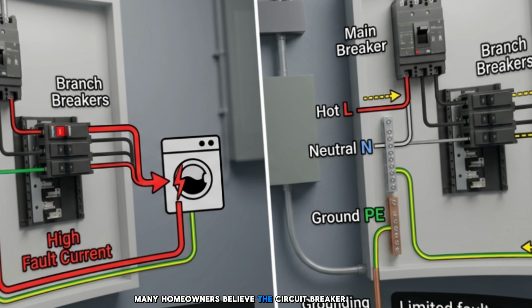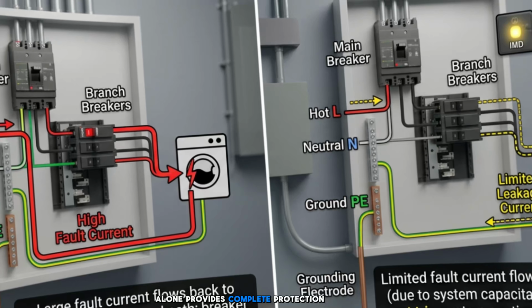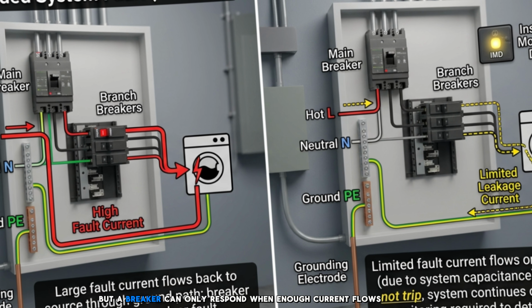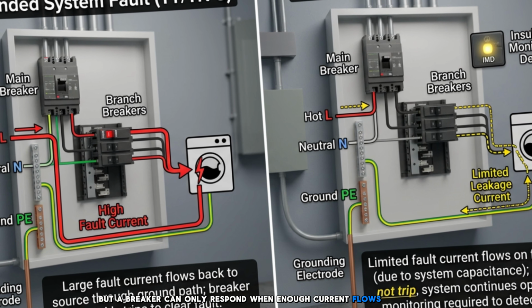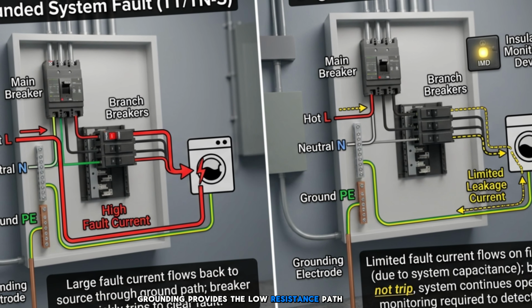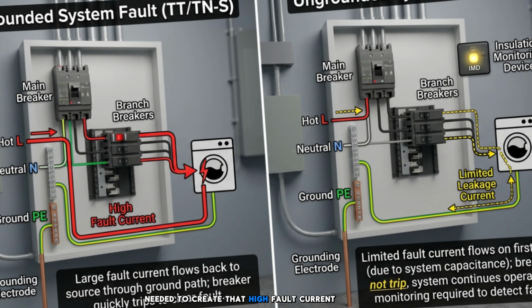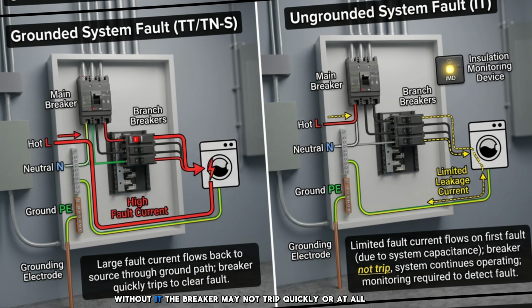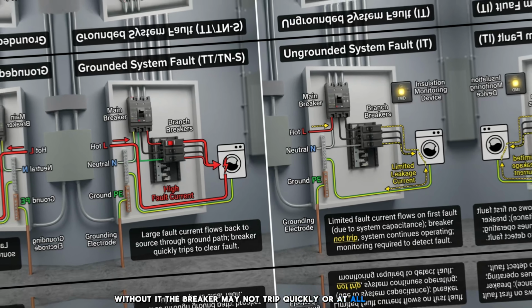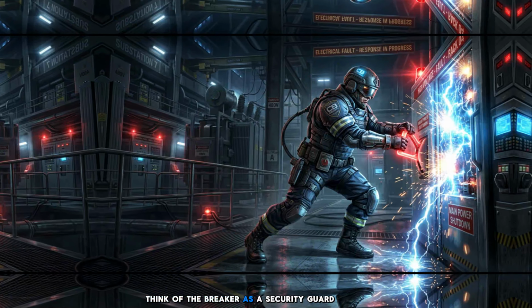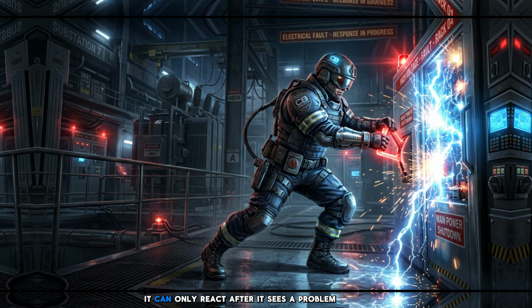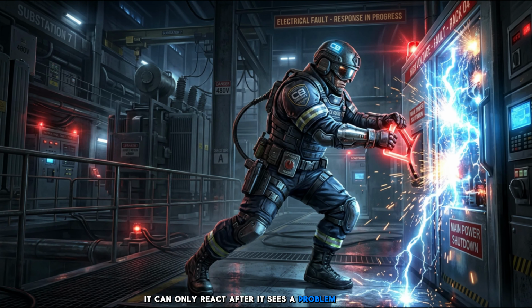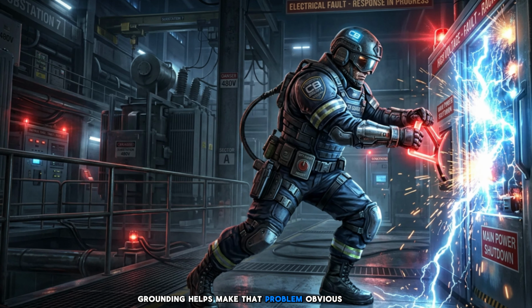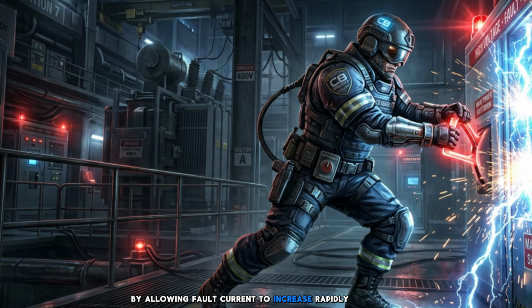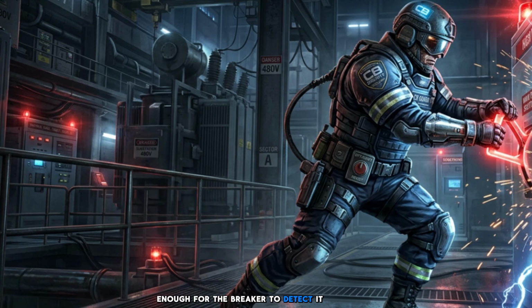Many homeowners believe the circuit breaker alone provides complete protection. But a breaker can only respond when enough current flows. Grounding provides the low-resistance path needed to create that high fault current. Without it, the breaker may not trip quickly or at all. Think of the breaker as a security guard. It can only react after it sees a problem. Grounding helps make that problem obvious by allowing fault current to increase rapidly enough for the breaker to detect it.